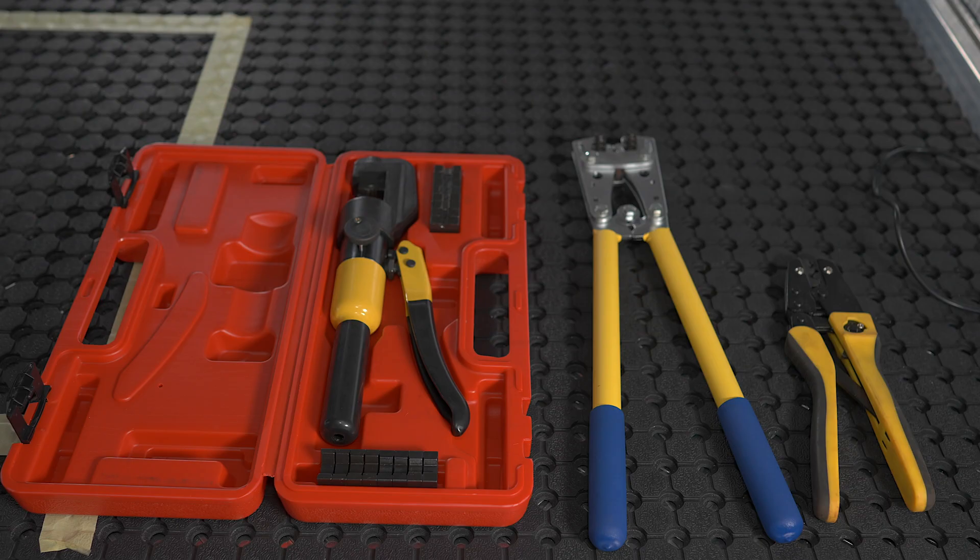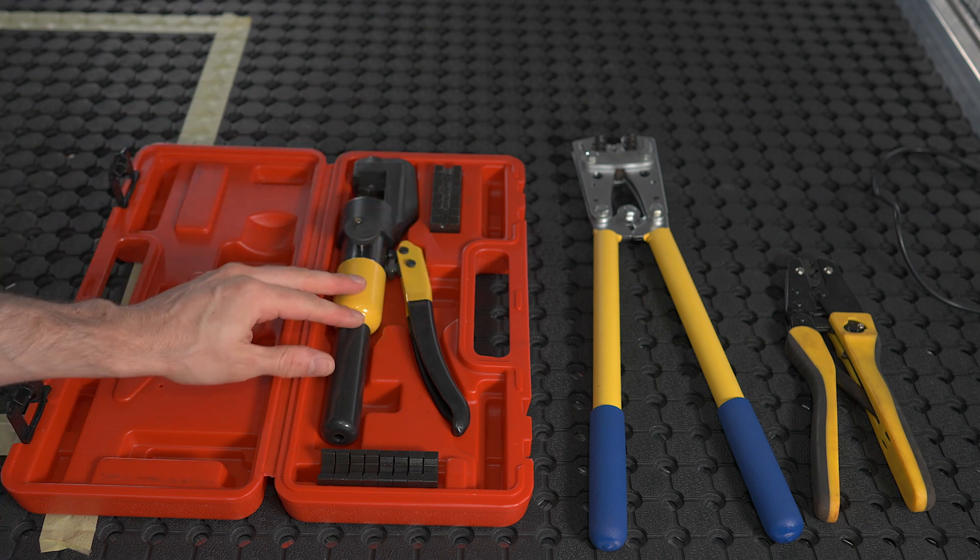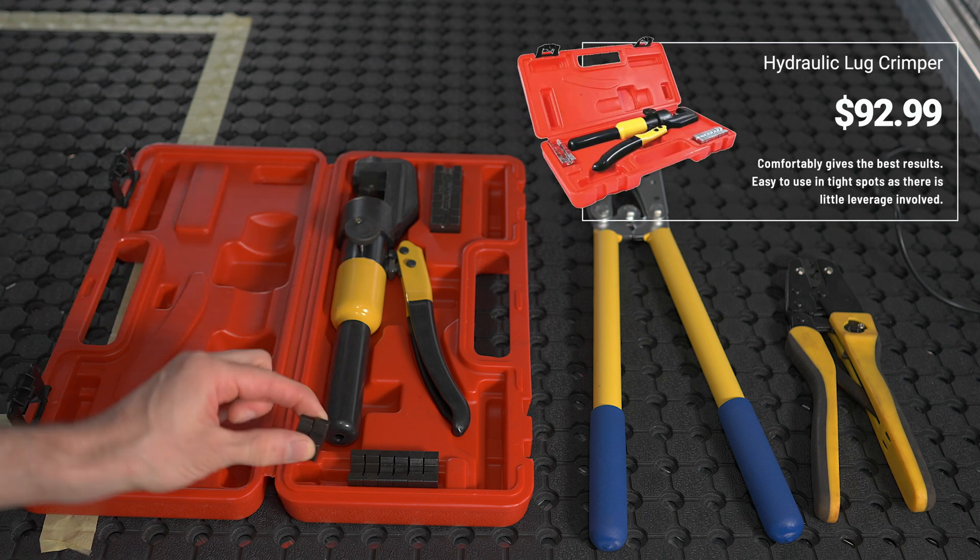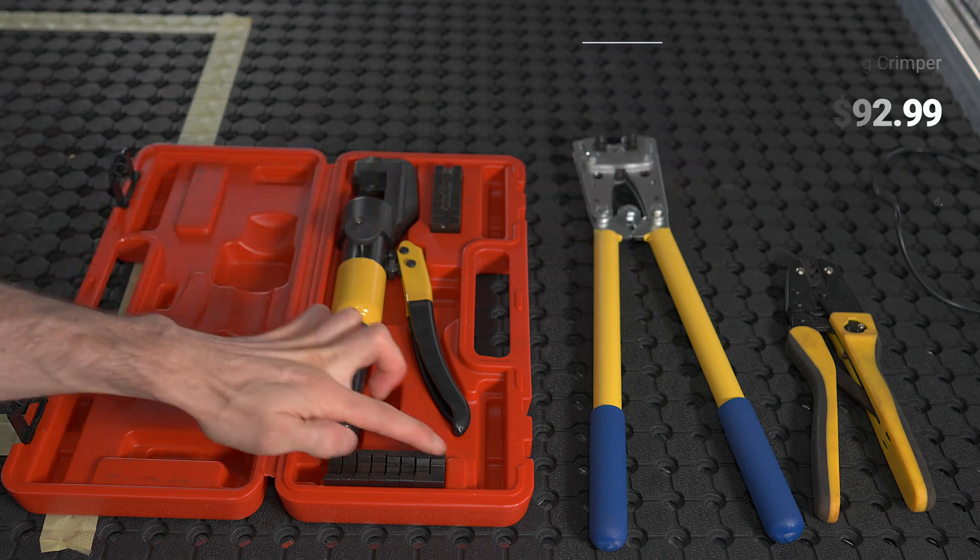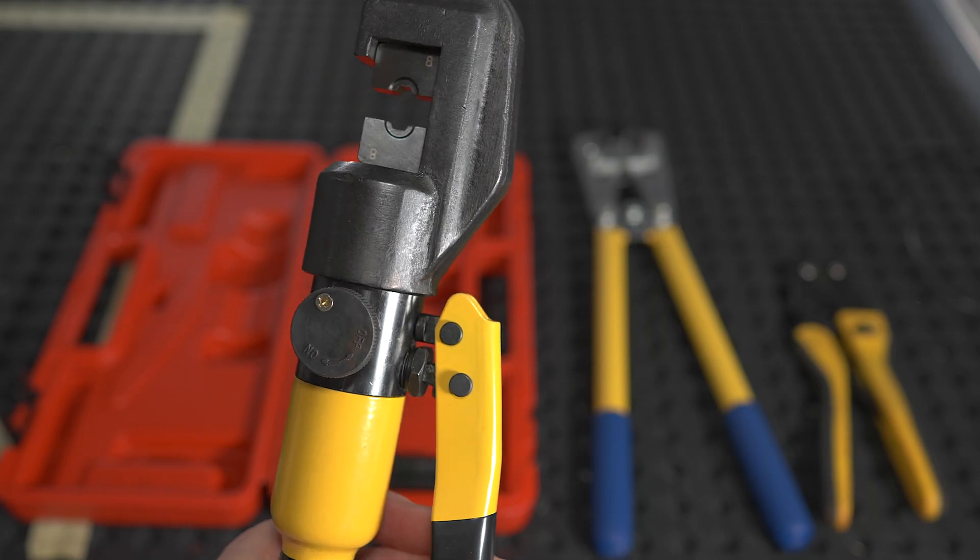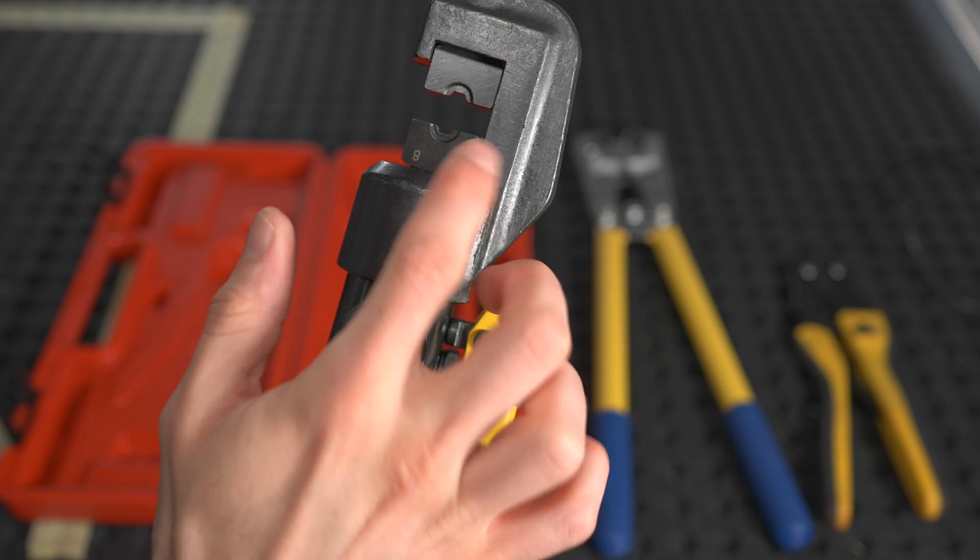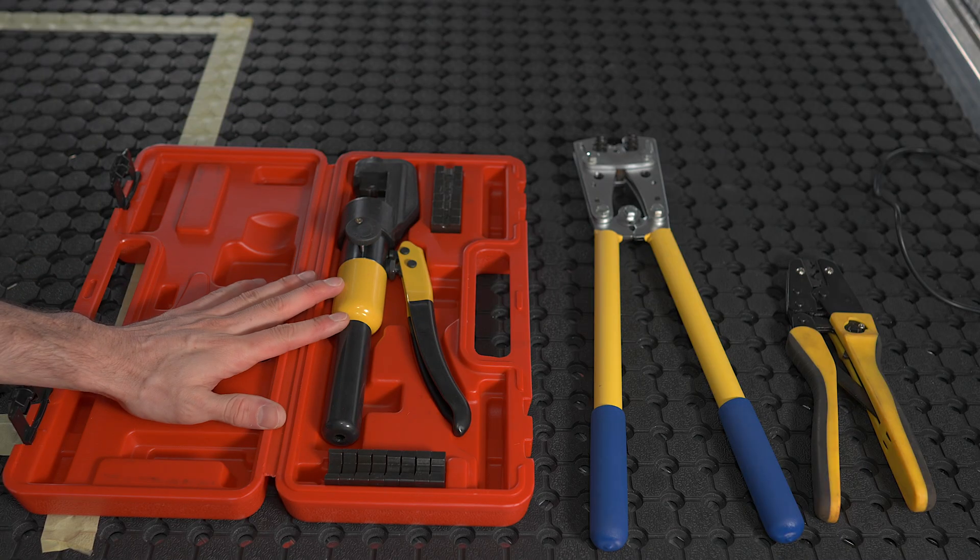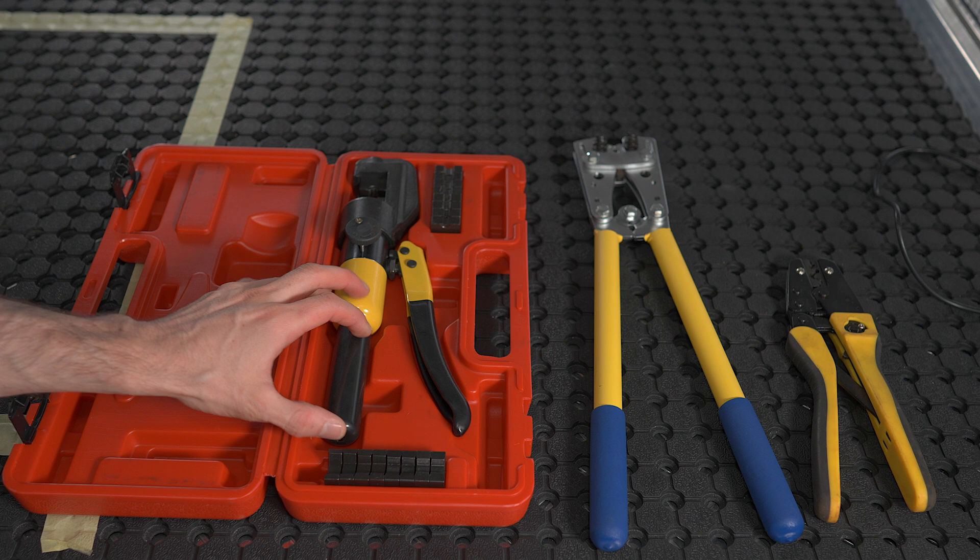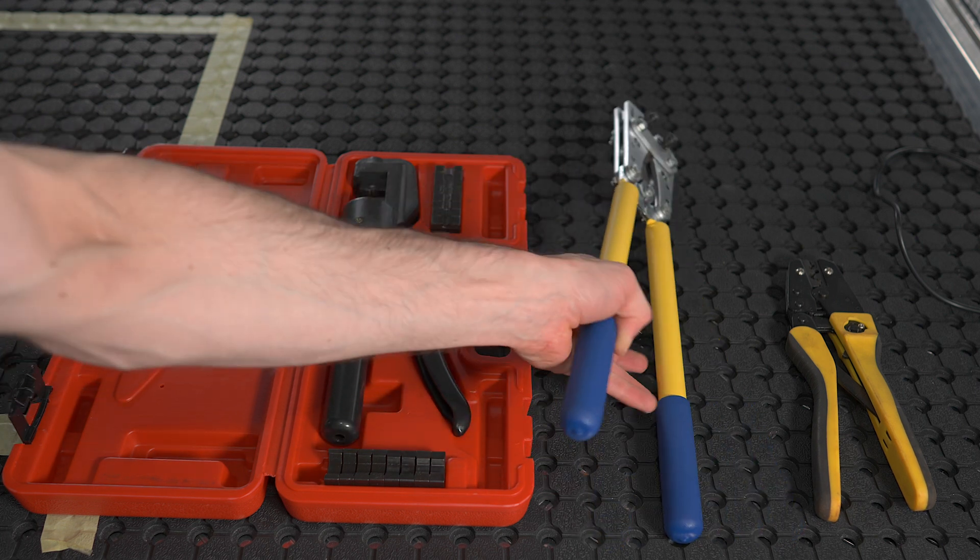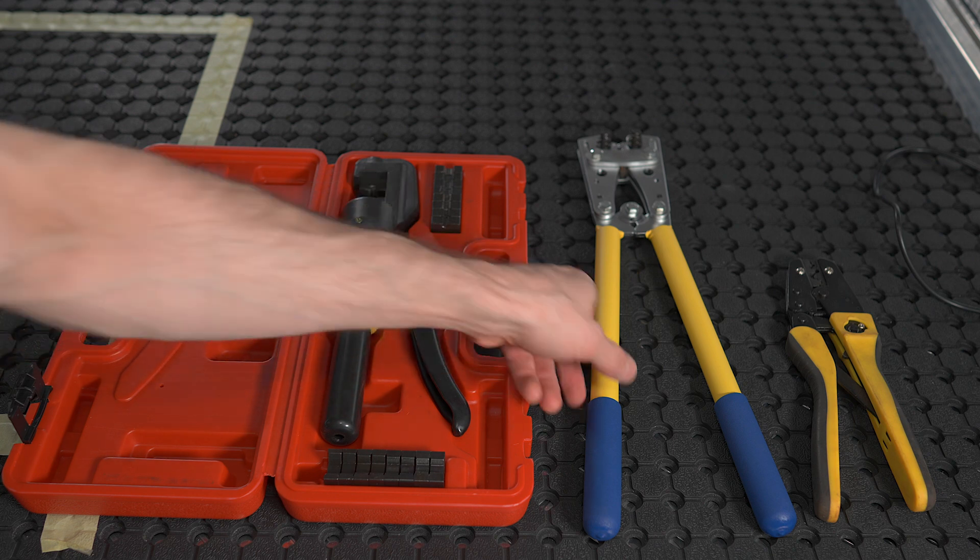In regards to crimping the Anderson plug or any cable for that matter, the best tool to use is something like this, which is a hydraulic press. They have different sized dies depending on what pack you buy. This does everything from 4mm all the way up to 70mm squared. The dies are marked so you can see what size you're using, and they give the best possible crimp. These are big solid bits of metal, they give you the perfect crimp. Not only is this the best tool for the job, it's actually also quite cheap for what you get. Considering a good pair of nutcrackers will actually cost you more than this hydraulic crimp and won't do as good a job.